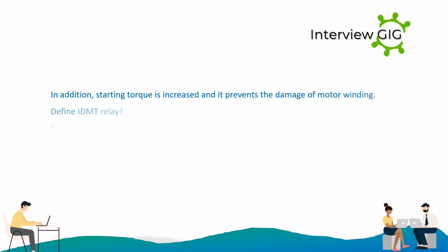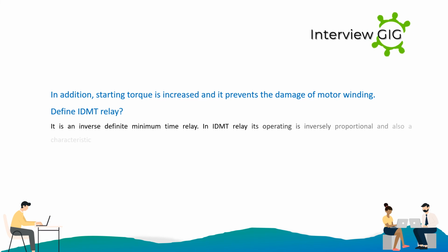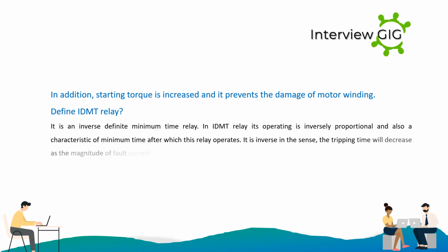Define IDMT relay. It is an inverse definite minimum time relay. In an IDMT relay, its operating time is inversely proportional and it also has a characteristic of minimum time after which the relay operates. It is inverse in the sense that the tripping time will decrease as the magnitude of fault current increases.